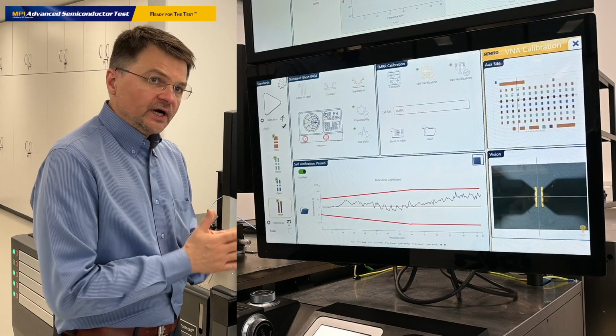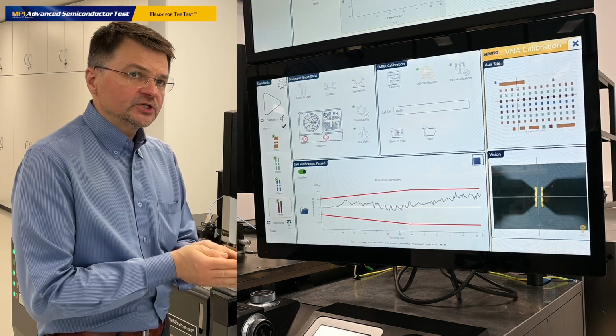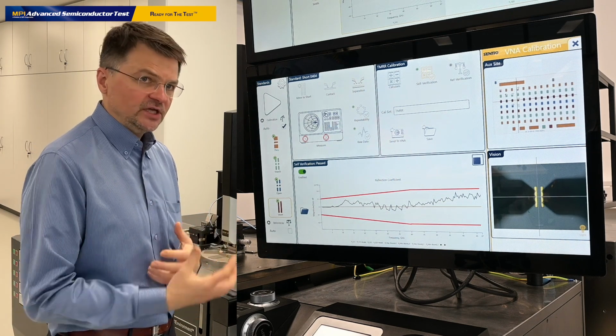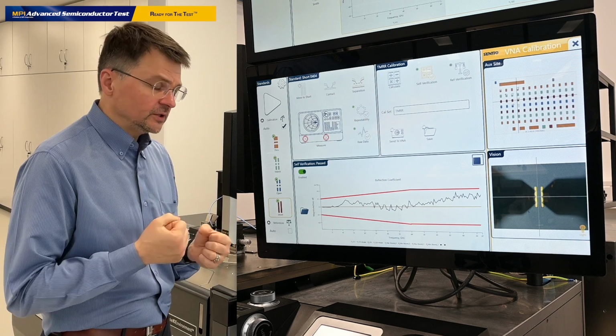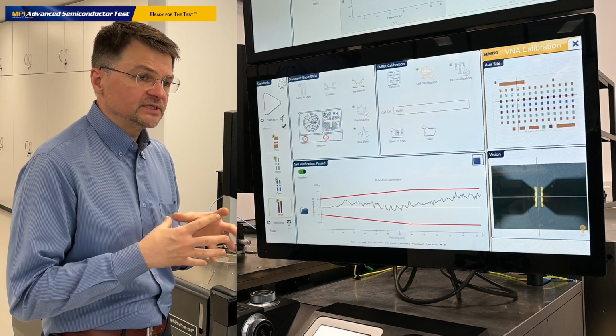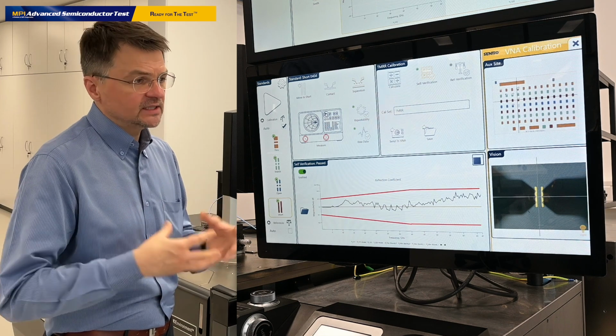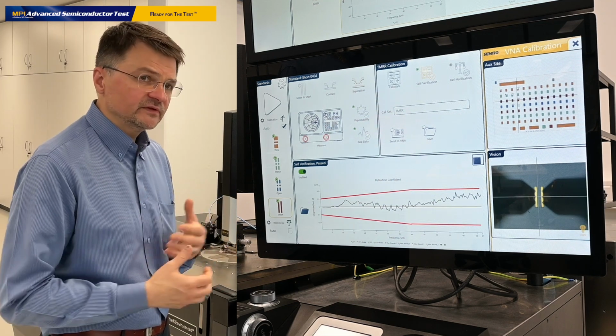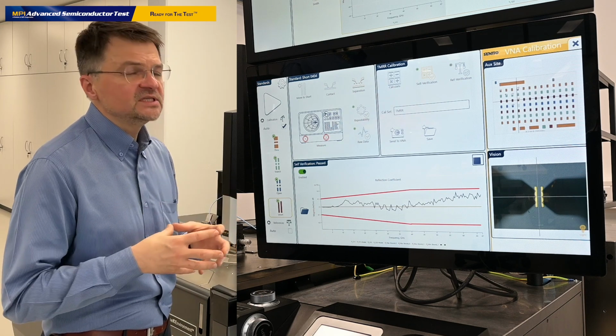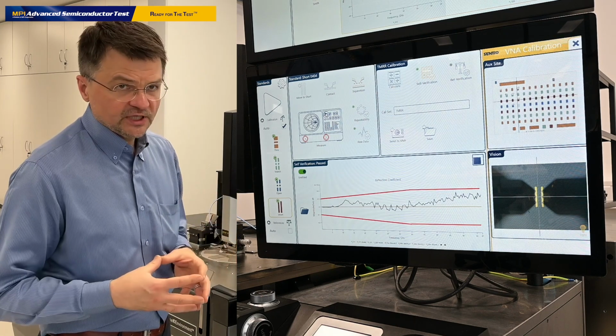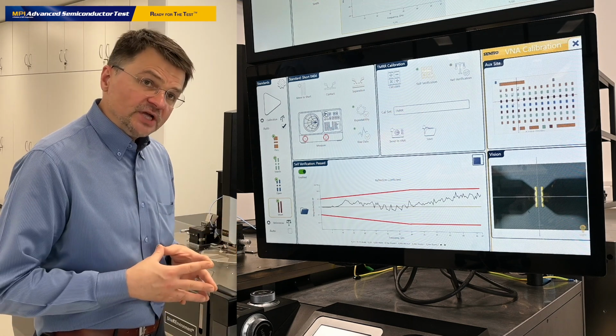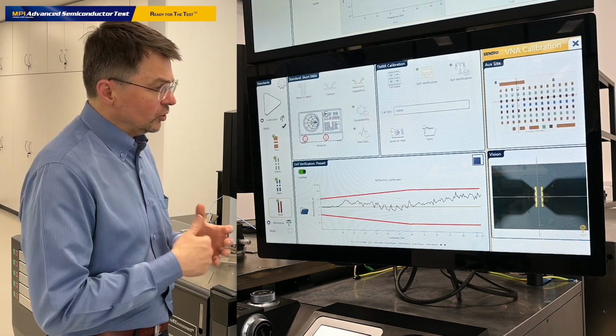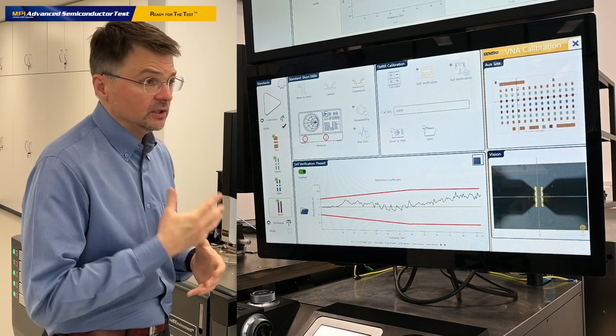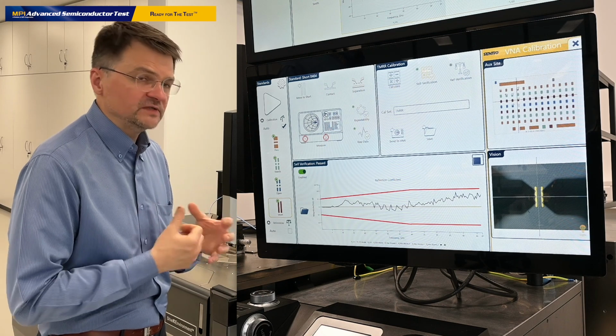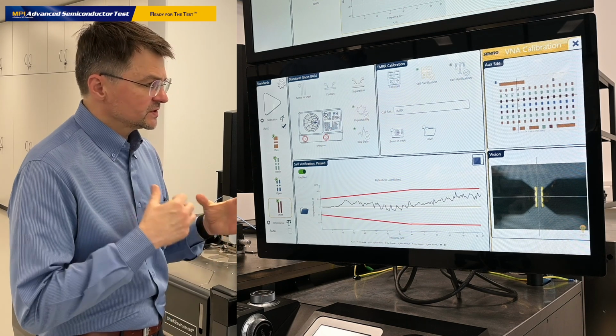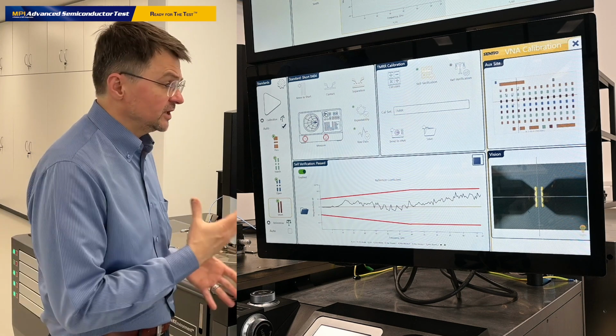There is another way to verify calibration quality. Not every calibration algorithm enables us the self-verification procedures. As we mentioned before, a calibration algorithm must be redundant, so we should measure more data than needed to compute error terms. Based on this information redundancy, we can qualitatively verify the accuracy of the calibration results. The simple calibration algorithms like SOL for one-port cal or SOLT for the two-port cal do not allow such powerful calibration quality verification algorithms, because there is no information redundancy acquired on calibration standards.